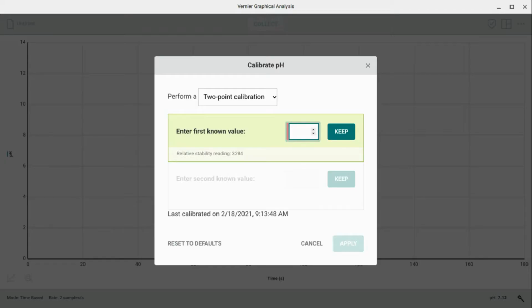Once the electrode is there, we should see the stability reading going down because the pH of the water was around 7.12, and it's going into a buffer of 4, which means that it's going to go down. We're going to wait for this reading level to stabilize, and once it's stabilized, we will put in the known pH value, which is again 4.00 plus or minus 0.02.